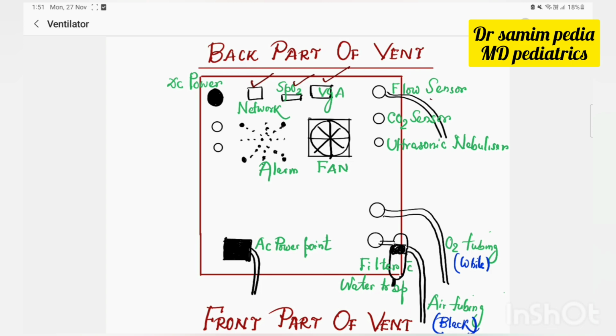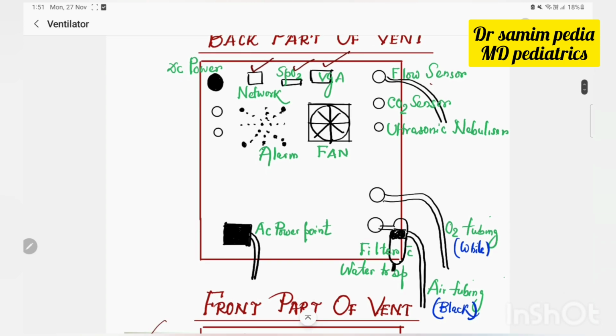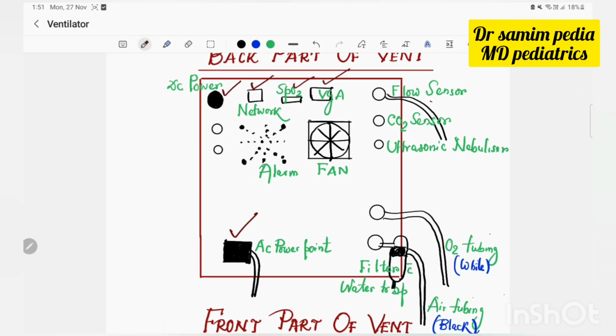In the back part of the ventilator, in the left lower corner there is the AC power point, and in the left upper corner there is the DC power point. In the upper part there are three squares. First one is for the network port, second one for the SpO2 sensor, and third one for the videographic array sensor. In the right upper corner there are three ports. First one is for the flow sensor, second one is for the CO2 sensor, and third one is for the ultrasonic nebulizer.